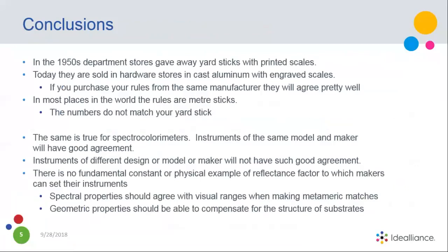We did a study when I was looking at this, and we took top-of-the-line instruments, and we had them in 4 different locations in the world. We sent the same reflectant materials, reference standards to them. They measured them. The agreement between the 4 instruments in 4 different parts of the world was better than 0.05 delta E.